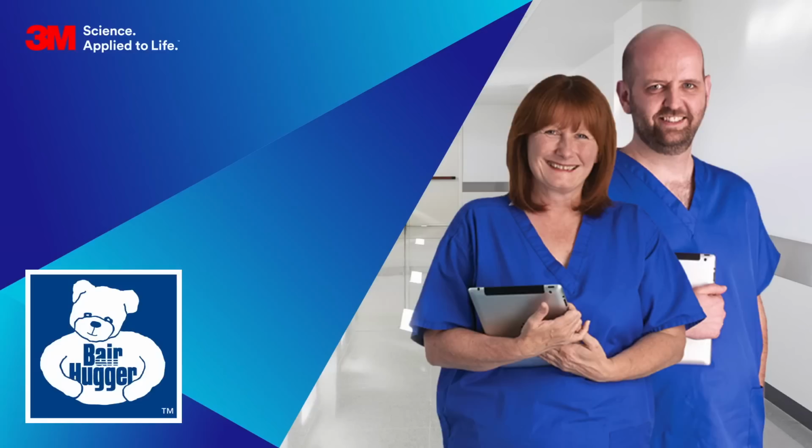So another question that we got from one of our customers is actually from an experience itself. The customer is using a support to position the patient's legs so the medial aspect are accessible for harvesting of the subcutaneous vein graft. The question that they have is, do we place the pad on top of the full access underbody blanket? If you could, you would position the support actually underneath the blanket so that you're still getting that support, but you're still getting a good airflow as well.